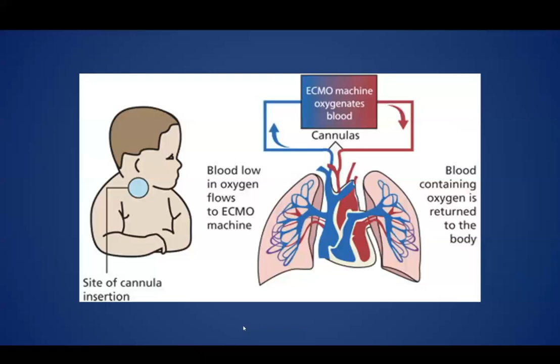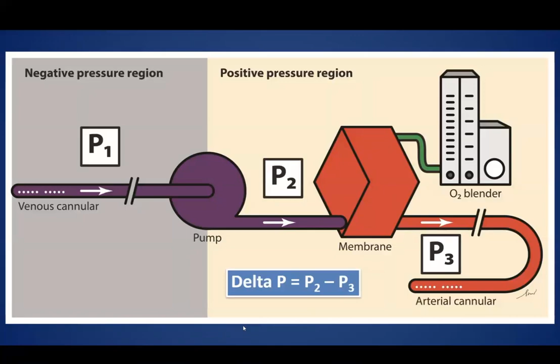Within the ECMO circuit, we can divide it into a negative pressure region located pre-pump, on the left side of the picture, and the positive pressure region post-pump, on the right-hand side of the picture. There are three sites of pressure measurement, namely P1, P2, and P3. P1 is located in the negative pressure region. P2 is post-pump, pre-oxygenator, and has the highest pressure in the system, and P3 is after the membrane before entering the patient. Delta P stands for transmembrane or trans-oxygenator pressure gradient, which equals P2 minus P3.